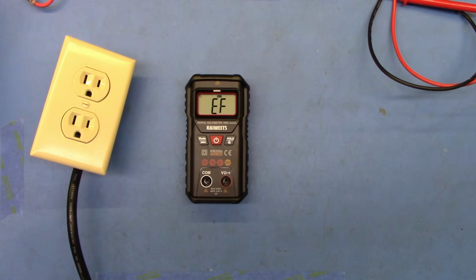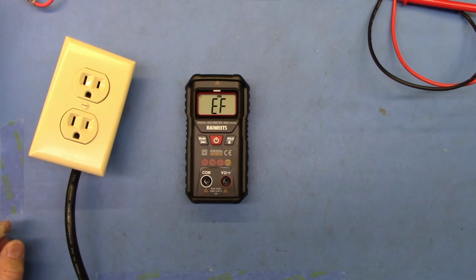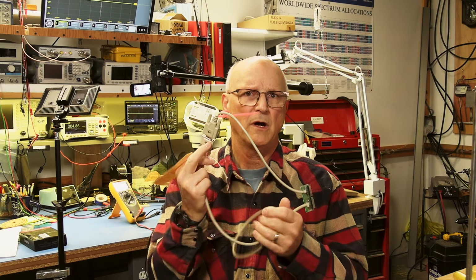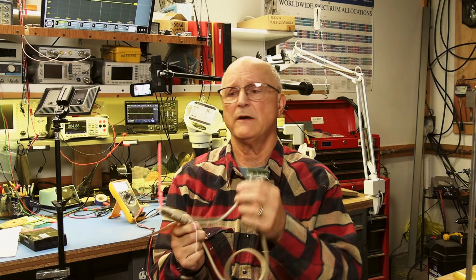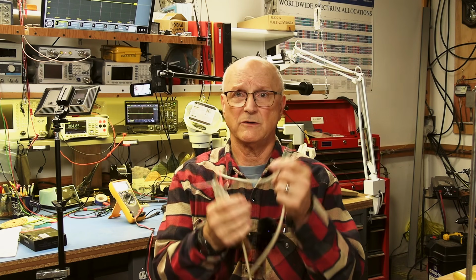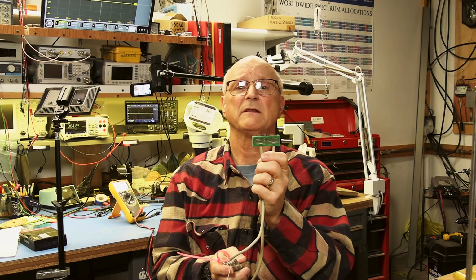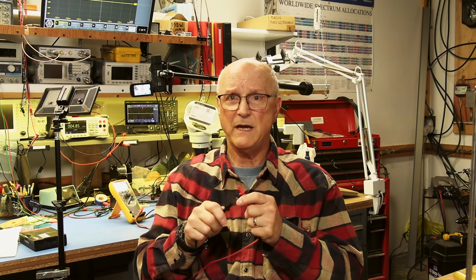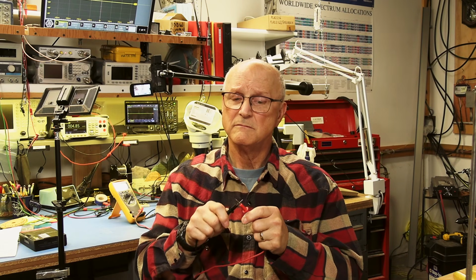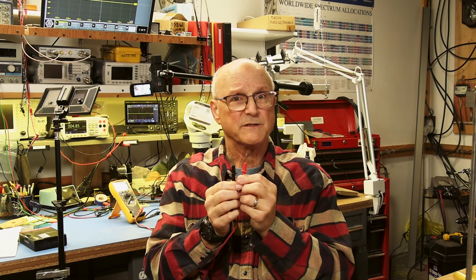All right, how about the continuity responsiveness? Well, when I'm using a continuity tester, I'm often checking pin-to-pin continuity on a cable. You know, pin 1 on one end should go to pin 3 on the other end, or maybe pin 1 on this end goes to what color wire exiting the other end of the cable. And, you know, I just want to be able to move quickly from pin to pin to pin. You know, I want immediate response when contact is made. So let's see how responsive this KM200s is when using the continuity function.